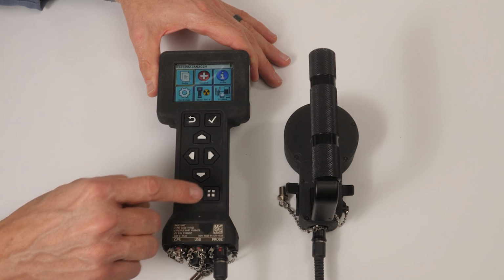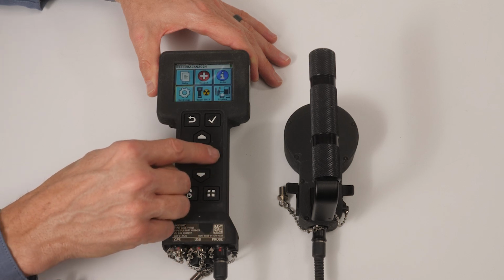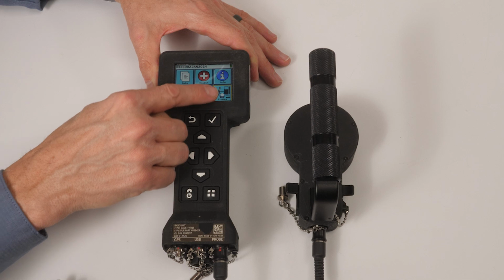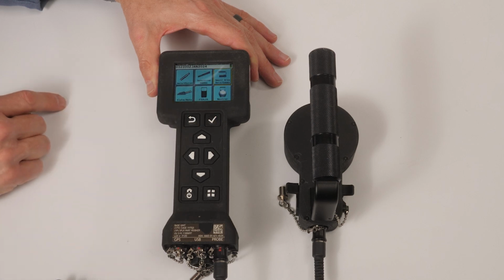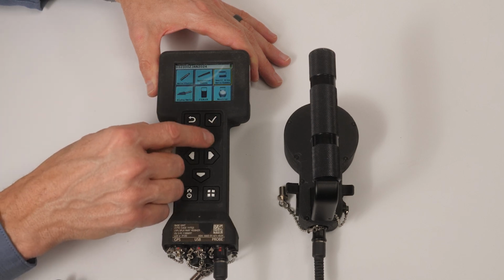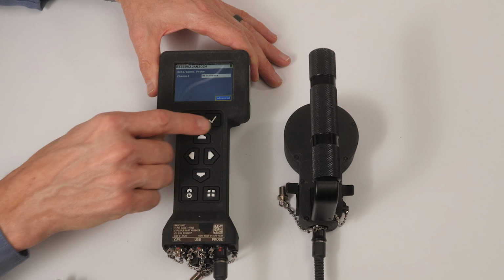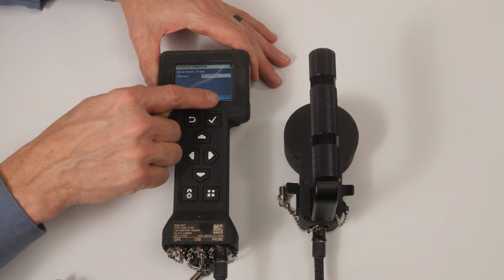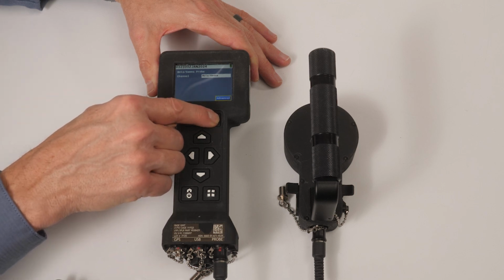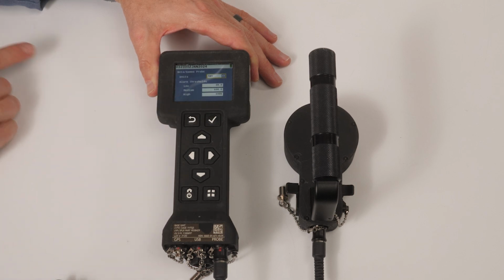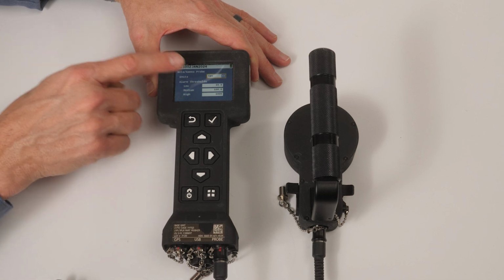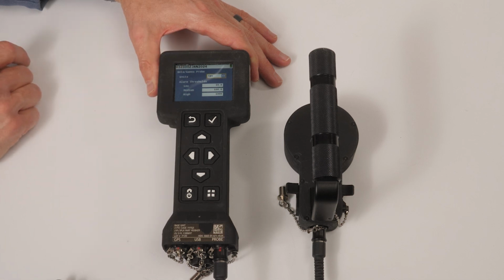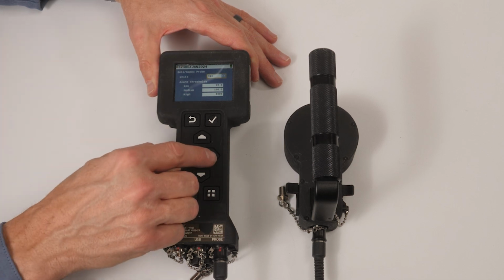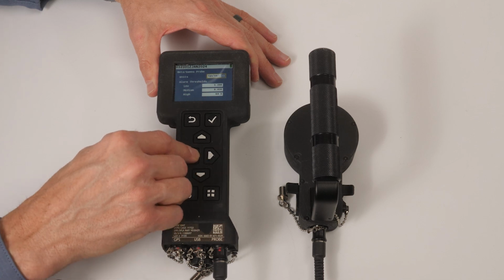To change radiation measurement units for the small area beta-gamma probe, press the menu key. Use the arrow keys to highlight probes, then press Enter. Use the arrow keys to highlight the small area beta-gamma probe icon and press the Enter key to select it. The Advance button will be highlighted as you enter this screen. Press the Enter key. On this screen, you can set the units of measure and alarm thresholds.